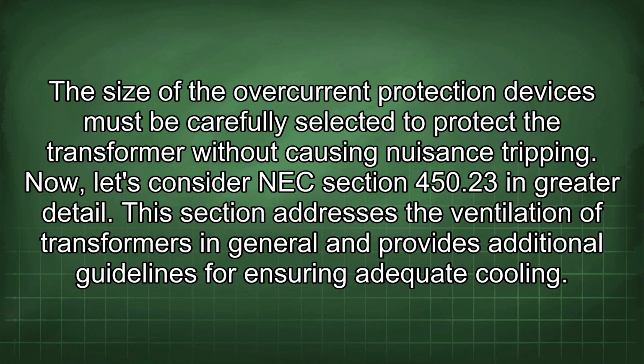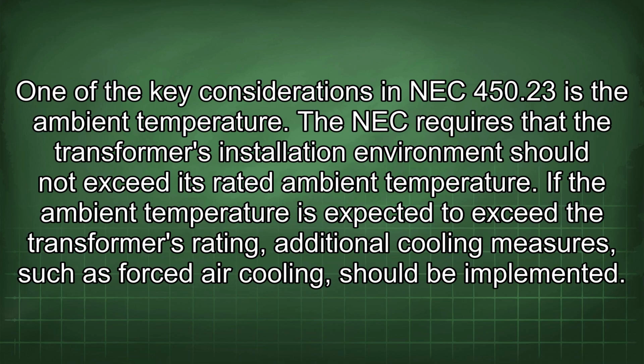Now let's consider NEC section 450.23 in greater detail. This section addresses the ventilation of transformers in general and provides additional guidelines for ensuring adequate cooling. One of the key considerations in NEC 450.23 is the ambient temperature. The NEC requires that the transformer's installation environment should not exceed its rated ambient temperature.